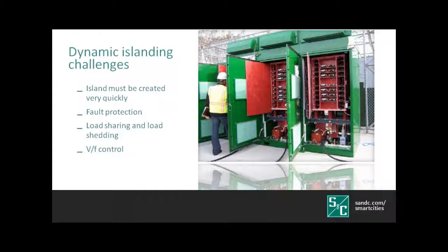If you're going to attempt to have a mission-critical or very sensitive piece of electronics connected to the microgrid, you need to create that island very quickly. One thing people often forget is that you have to coordinate faults differently in a microgrid compared to the overall grid. There's not as much short circuit current available in an island situation, so you have to adjust fault protection to account for that. As discussed earlier, with load sharing and load shedding, you're trying to prioritize critical applications first and less sensitive applications second to match available generation. It's also available to do voltage and frequency control to keep everything organized and running properly.